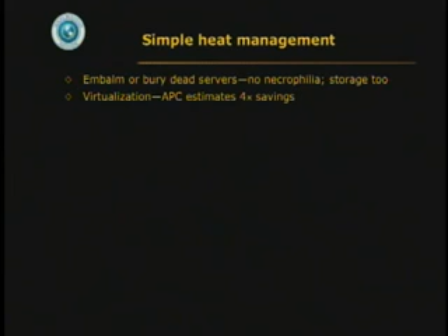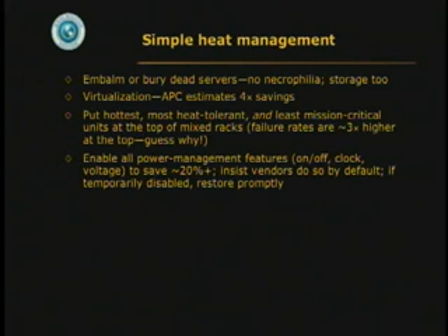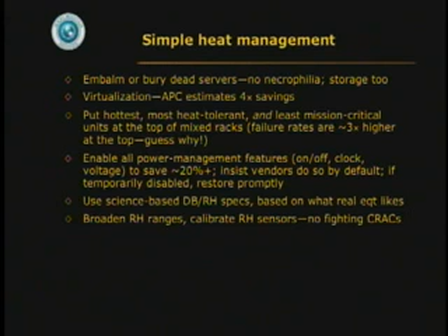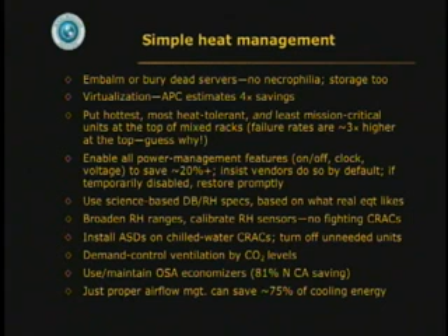Put the hottest stuff and the most heat tolerant and the most unimportant to your mission up on top where the failure rates are higher because it's hotter. Put the critical stuff toward the bottom of each rack. Enable all your power management features, big savings. Use science-based specs for humidity based on what your equipment actually likes, not an assumption. Often you have one CRAC that is trying to dry the air, another that is humidifying the air, sitting right next to each other, fighting each other. Use variable speed drives, turn off unneeded units, demand controlled ventilation, outside air economizers, 81% saving in Northern California from doing that. And just proper airflow management in a typical data center can save about 3/4 of the cooling energy.